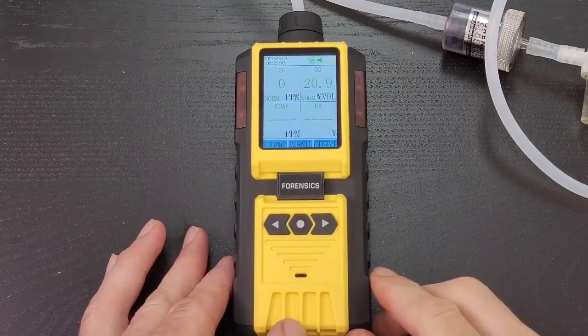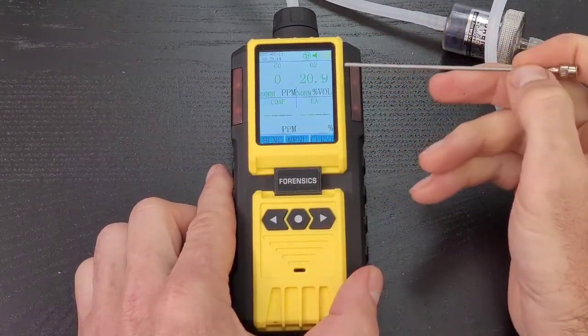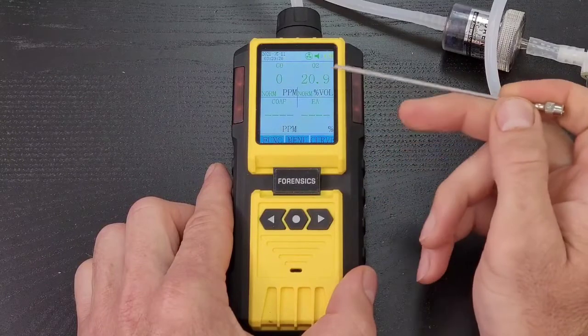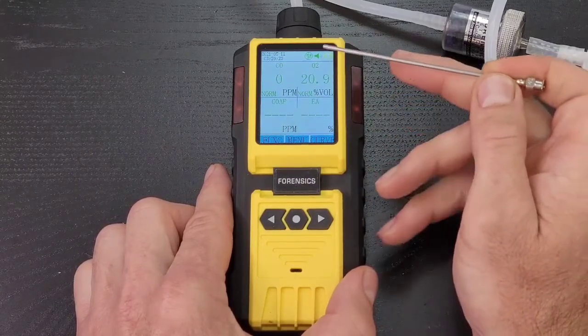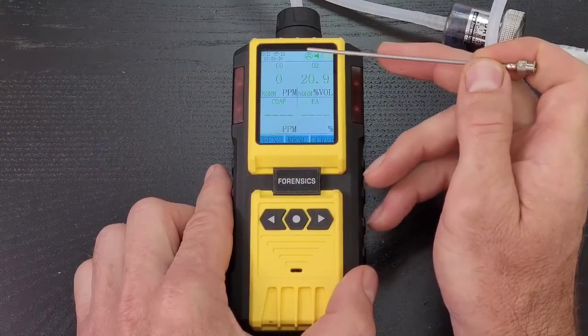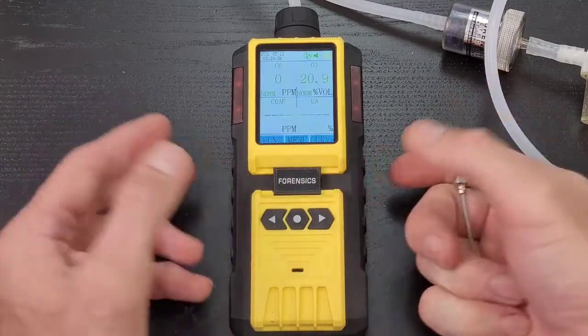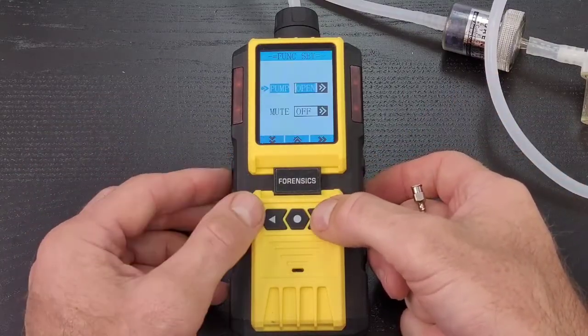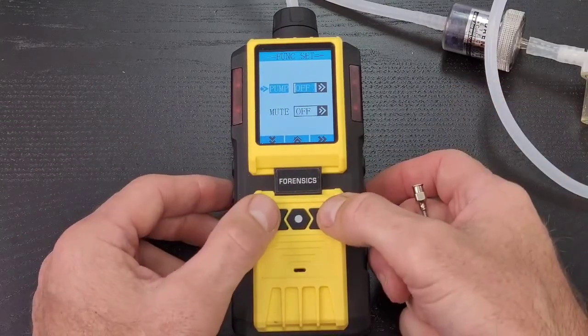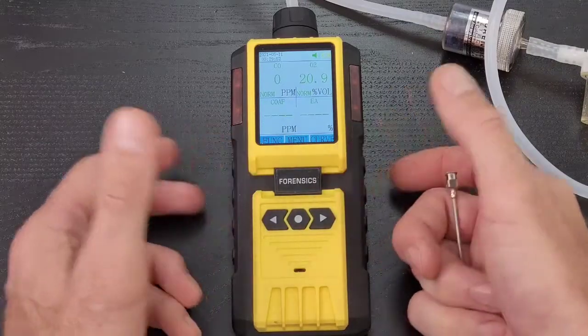I've gone and magnified the camera so you can see the screen a little bit better. What's going on? We have our oxygen display, 20.9. We have our carbon monoxide display. We have our excess air and COAF, everything on one screen. On the top, we have our battery indicator. We have our alarm speaker, if it's on or off. And we have that rotary fan, which is telling you that yes, the micropump is working, everything's normal, the date and time. Please read your manual, but I'll show you very quickly what's going on. If you want to stop the pump because you want to save some power, you're sort of on standby, just press that left button and turn off the pump. If you're setting your alarms, you could turn on and off and mute that function also. So for now, we'll turn off the alarm.